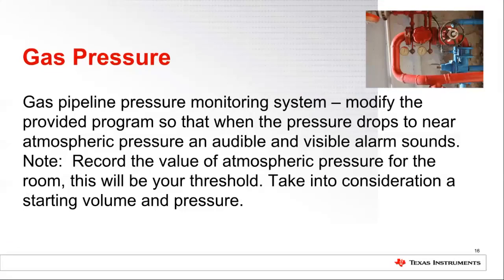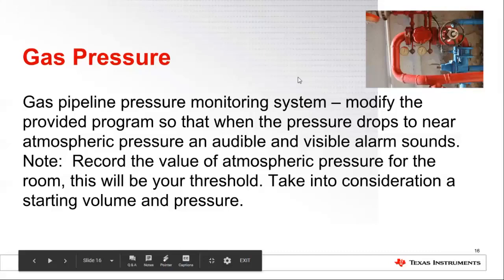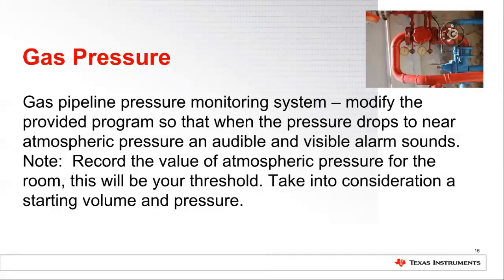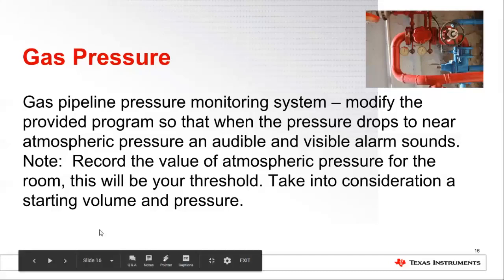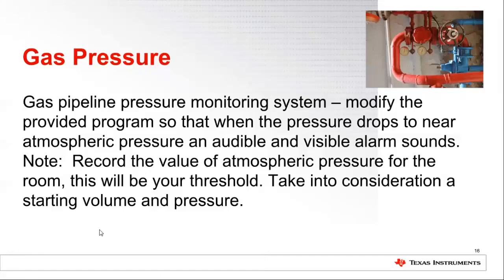Other pressure monitoring systems we can now simulate with this SensorLink and gas pressure sensor include, for example, gas pipelines. There are monitoring systems built in along pipelines that indicate if there's a sudden drop in pressure. The program we'll show you is a very simple simulation that assumes when the pressure in the pipeline drops to near atmospheric pressure, there's a response: an audible, visible alarm will sound. So one of the things we have to establish in the program is the value of atmospheric pressure, and what happens when that pressure threshold is reached from an initially higher value.